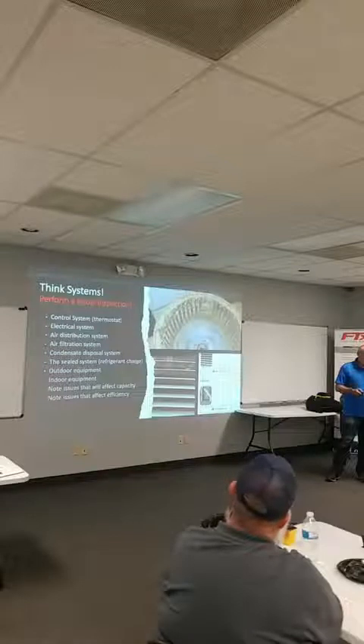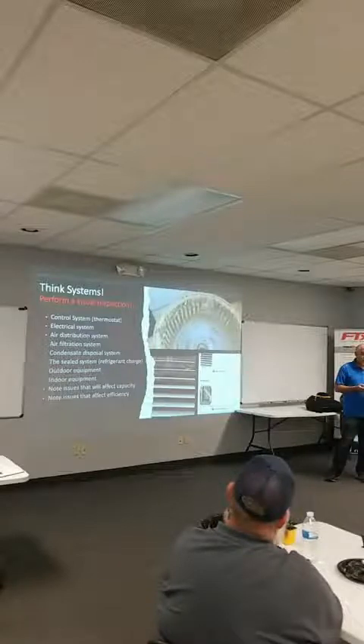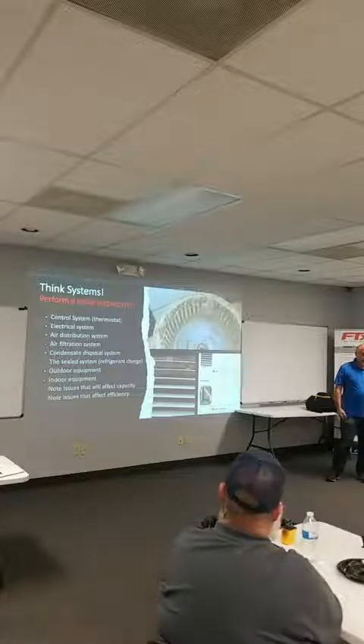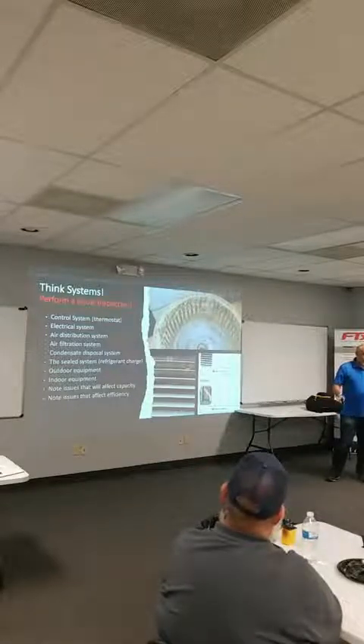There is no way to get moisture out of a POE oil with a vacuum pump. It's impossible. It bonds at a molecular level. The only way to get it out is with a desiccant dryer, that's it. So as soon as you heat the dryer up, you've pushed all the moisture back in the system. You may as well not even take it out in the first place. If you're not gonna cut it out, just don't even take it out, because you're better off probably leaving the damn thing in there, right?